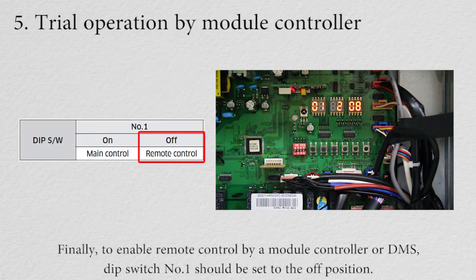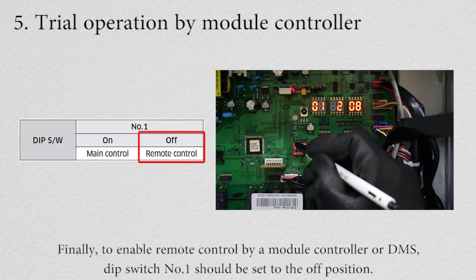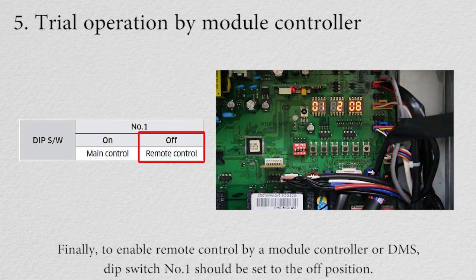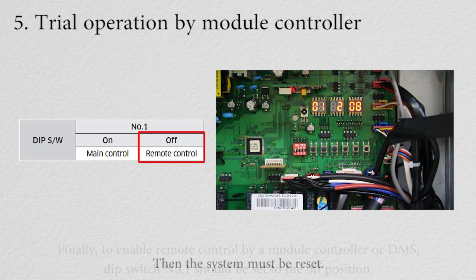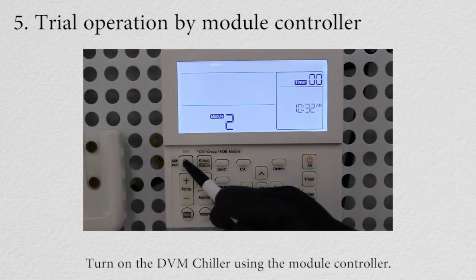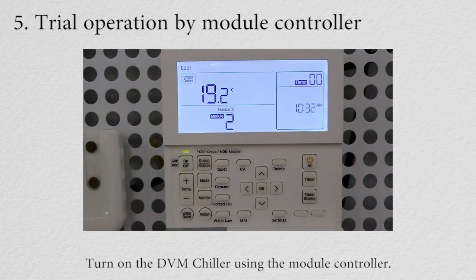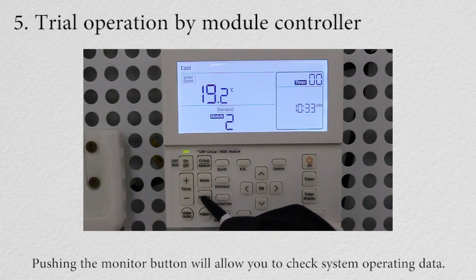Finally, to enable remote control by module controller or DMS, dip switch number 1 should be set to the off position. Then the system must be reset. Next, turn on the DVM chiller using the module controller. Pushing the monitor button will allow you to check system operating data.